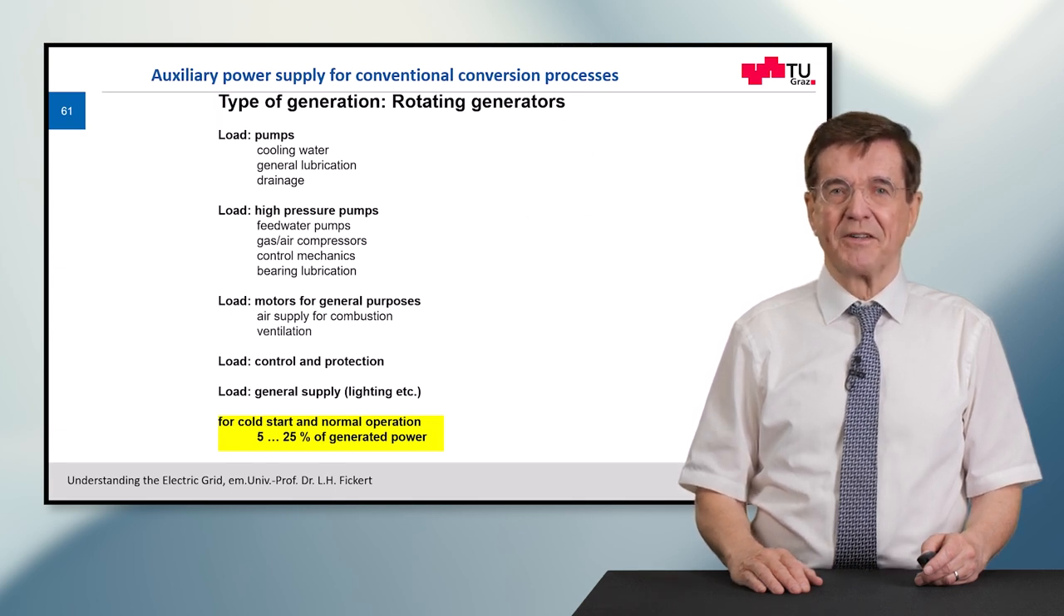For cold start and normal operation of such a conventional conversion process, we need something between 5 to 25 percent of the generated power. If in the case of a black start and a blackout this energy is not available on site, such a power station cannot start up. Here you can see that these auxiliary power supplies play a very important role for the survival of our electricity system.